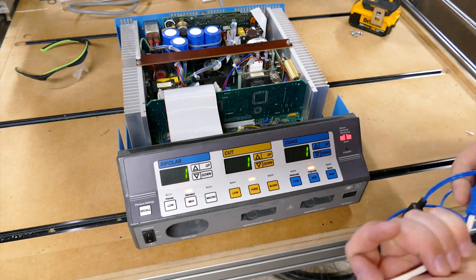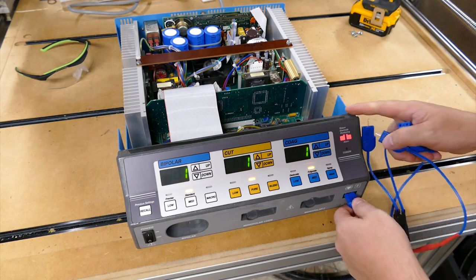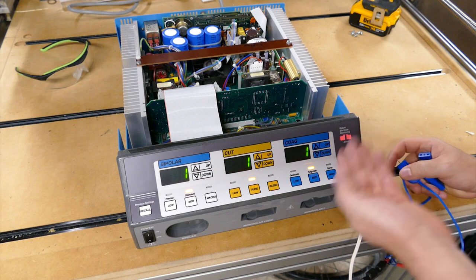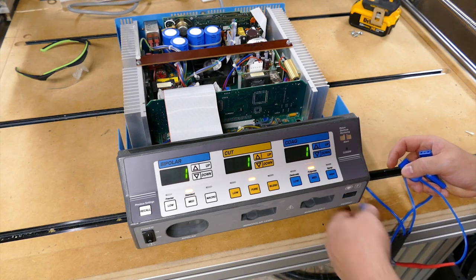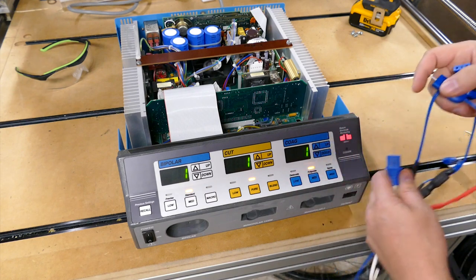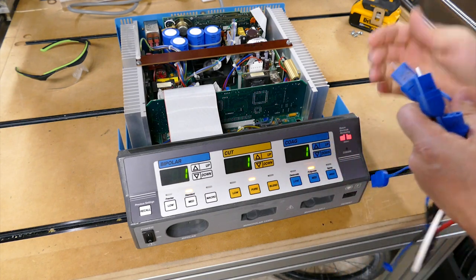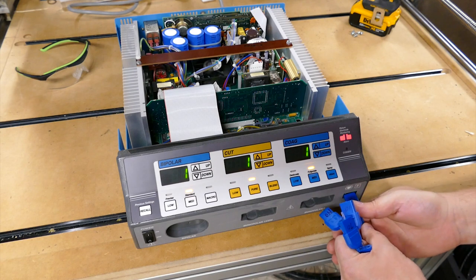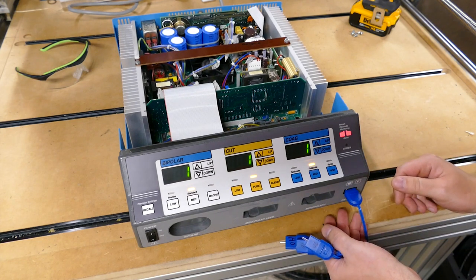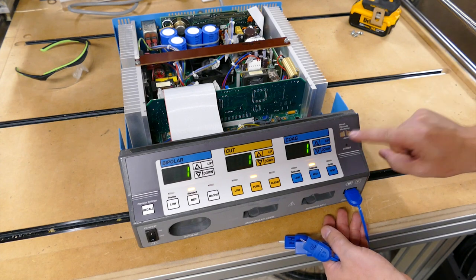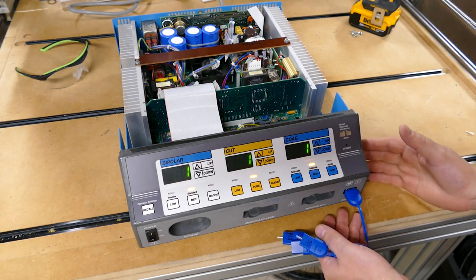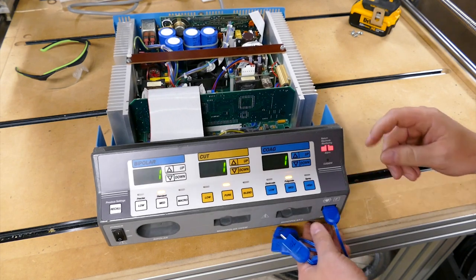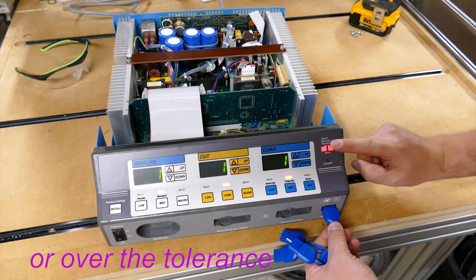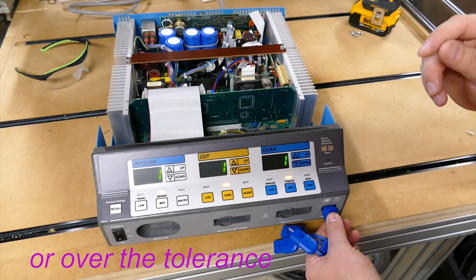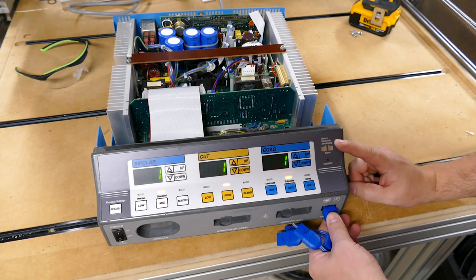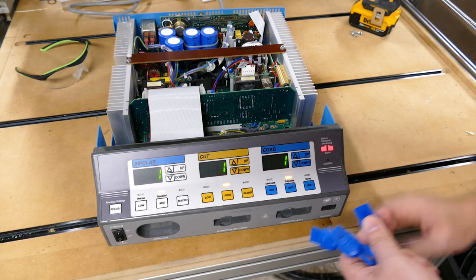You're supposed to be able to go to 135. You can see I'm getting a red alarm. That one is actually 137 ohms. Let's see, where is my 130? Here's 130. Okay, 130 ohms, it should definitely be showing green. We're starting to see this trend with these units all over the place where they'll go under the tolerance and they'll still show an alarm condition, to which you will get callbacks on this exact device. And callbacks will just make everybody upset.